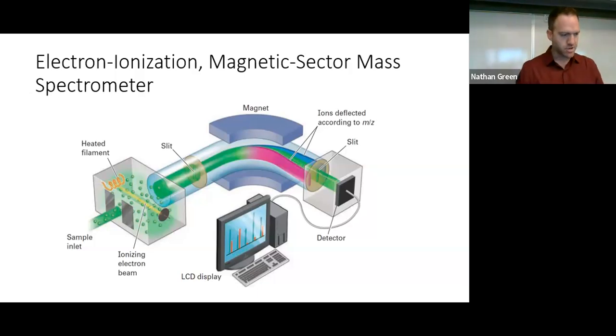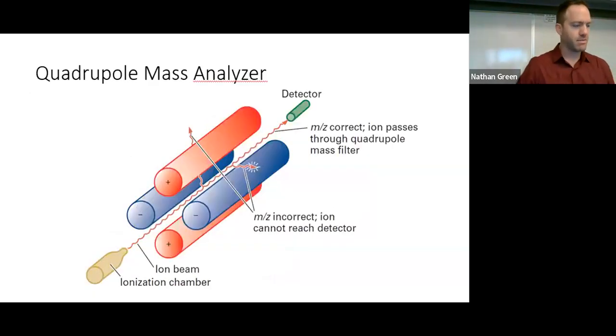We've been able to miniaturize it by using a very similar idea, but called a quadrupole. It's called a quadrupole because it has 4 poles. So quad pole. What we do here is we put charges on the poles. So pluses on one side, minuses on the other side. And you can change the amount of positive and negative potential in these rods so that as your sample moves down through here, it'll get pulled one way or the other.